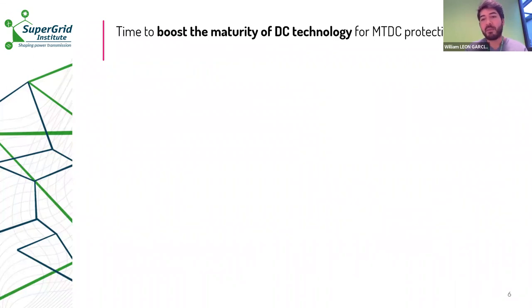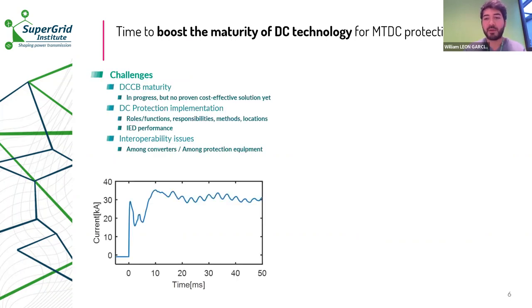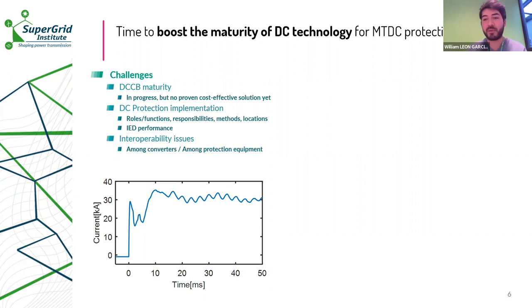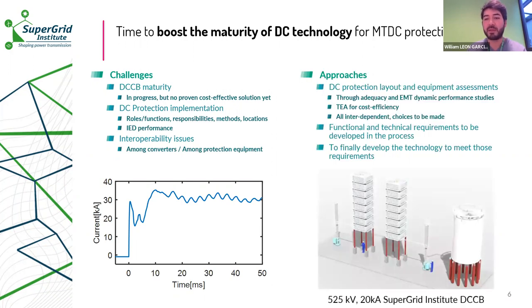To ensure reliable MTDC projects, we need robust protection. One challenge is the maturity of DC circuit breakers — since the DC current doesn't cross through zero, it can reach high peak values in a multi-terminal system. We need to think about DC protection from the algorithm to the DCCB and beyond. Another challenge is interoperability issues among different converters and among different protection equipment and strategies. To overcome these challenges, we need to assess the DC protection layout, the equipment necessary, what is the most cost-effective solution, and evaluate performances using EMT (electromagnetic transient) simulation.